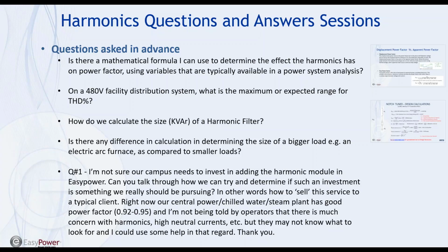Another key thing to remember is that voltage distortion affects all loads in a system. So when you have high voltage distortion within a plant, you're impacting all electrical loads because they are connected in shunt with the network. They are seeing that voltage. So voltage distortion is a key design parameter when designing your network, and 5% is a good target number to start with within the network itself.